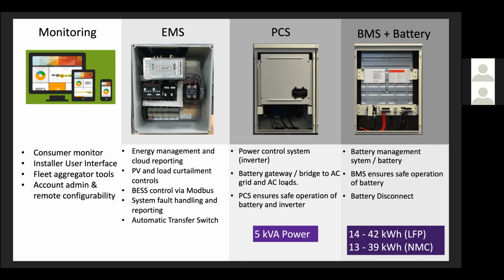The DC component, the BMS and battery, what's shown here is from the ESS system. The LFP cabinet looks a little bit different. The batteries are just oriented differently inside the battery cabinet and are just interconnected slightly differently. Those differences are detailed in the installation manual. So please, if you've installed one and you're going to install the other, make sure that you take a look at that other manual. The DC cabinet consists of the battery management system and battery, obviously.